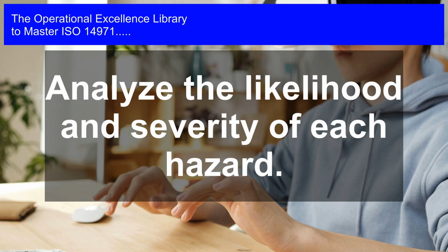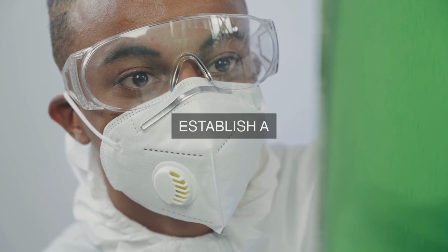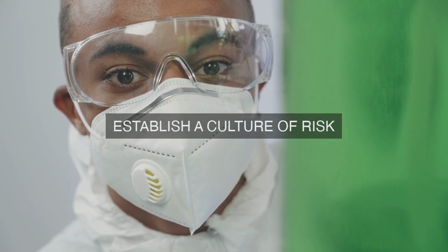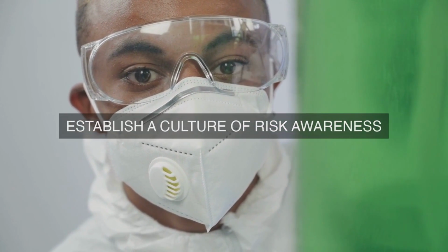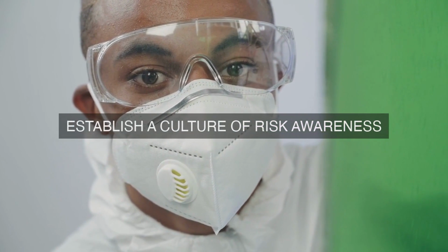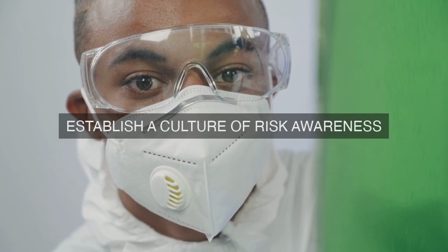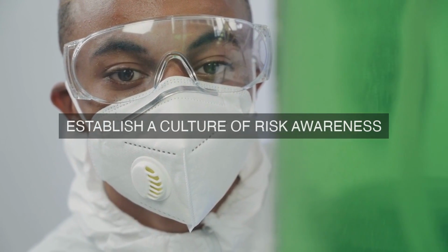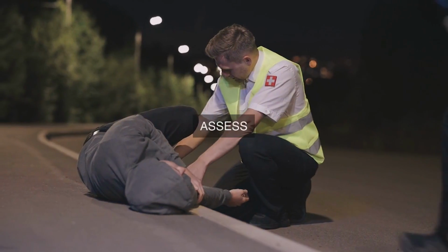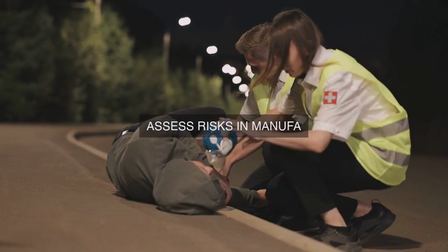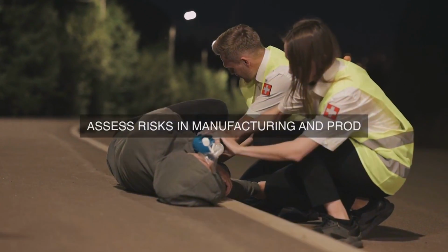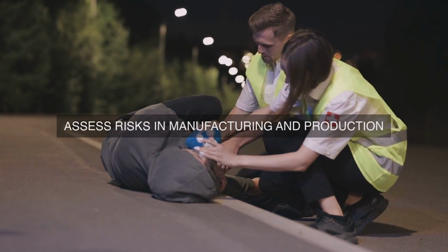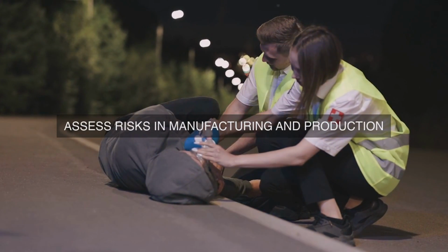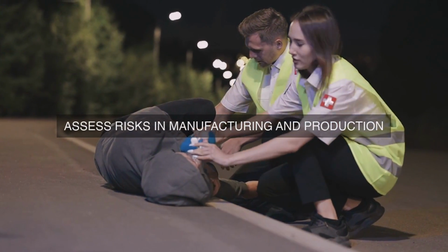The risk management process outlined in ISO 14971 involves the following steps. 1. Risk analysis. This involves identifying and describing potential hazards associated with a medical device. This can be achieved through a thorough analysis of the device's design, materials, manufacturing process, and intended use. The analysis should consider various factors, such as the device's functionality, user interface, and environmental factors.